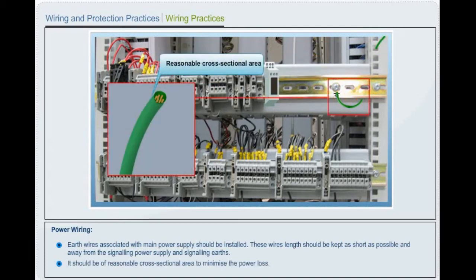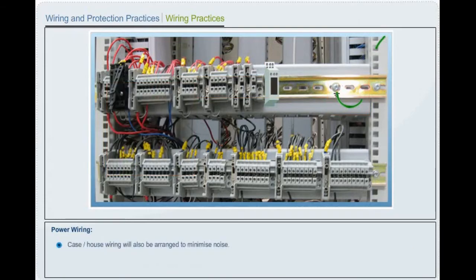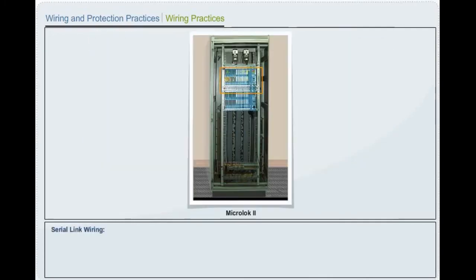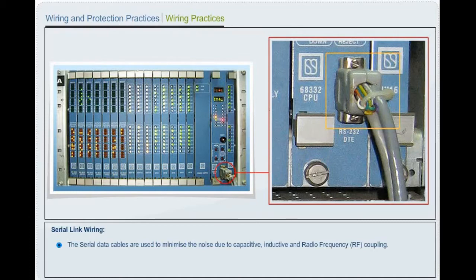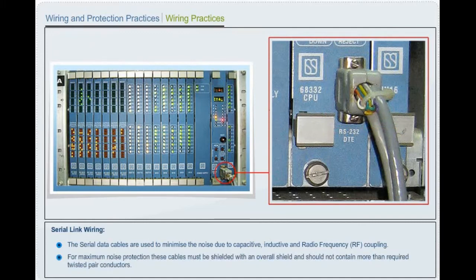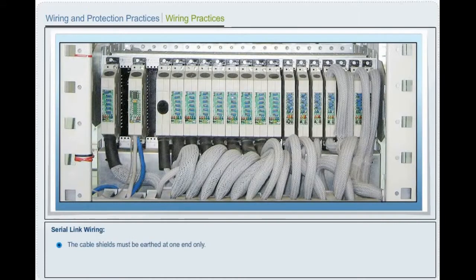It should be of reasonable cross-sectional area to minimize the power loss. Case or house wiring will also be arranged to minimize noise. Serial link wiring. The serial data cables are used to minimize the noise due to capacitive, inductive, and radio frequency coupling. For maximum noise protection, these cables must be shielded with an overall shield and should not contain more than required twisted pair conductors. The cable shields must be earthed at one end only.